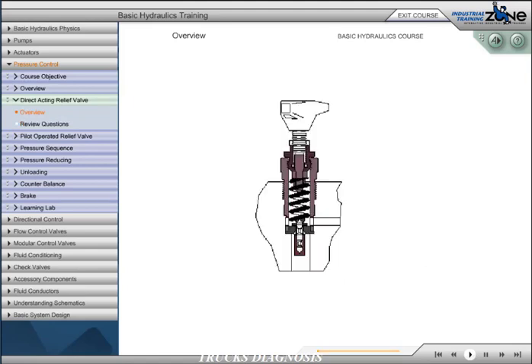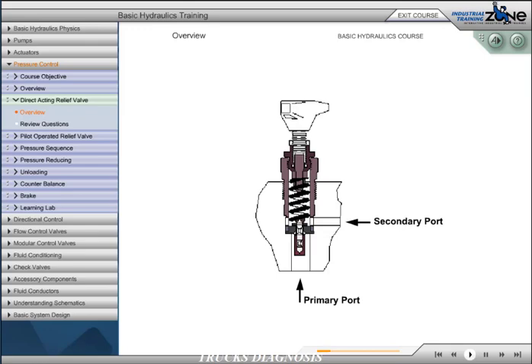Maximum system pressure can be controlled with the use of a normally closed pressure valve. With the primary port connected to system pressure and the secondary port connected to tank, the poppet is actuated by a predetermined pressure level, at which point primary and secondary passages are connected and flow is diverted to the tank. This type of pressure control is known as a relief valve.